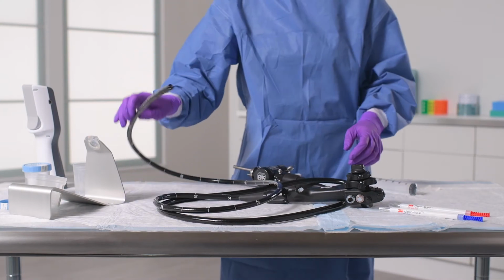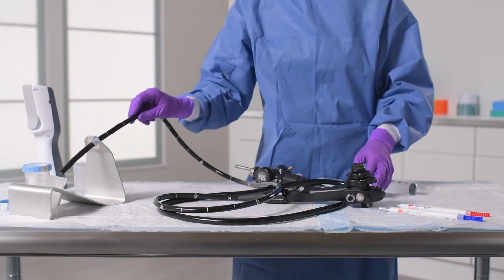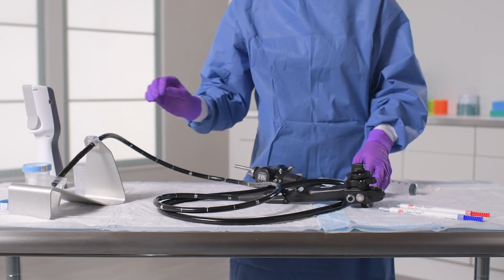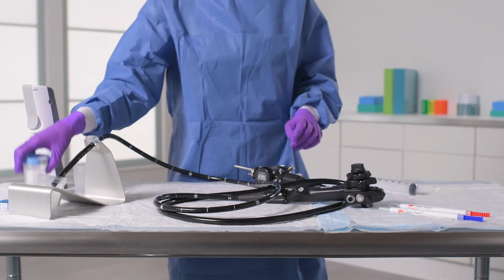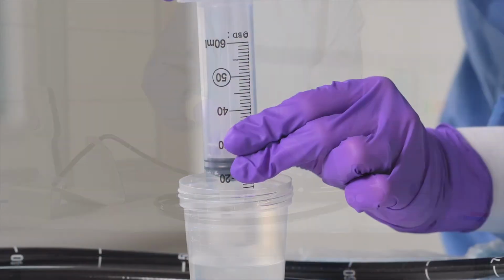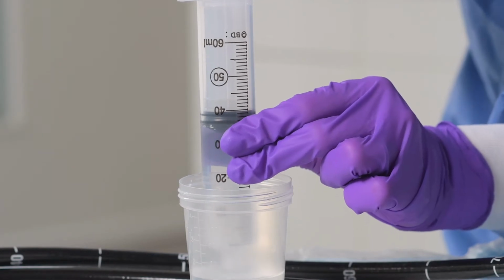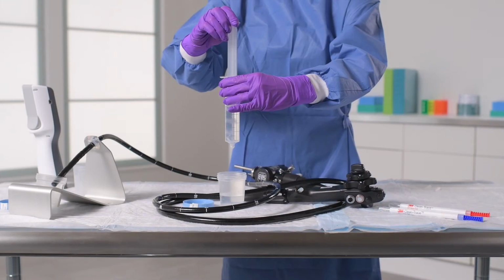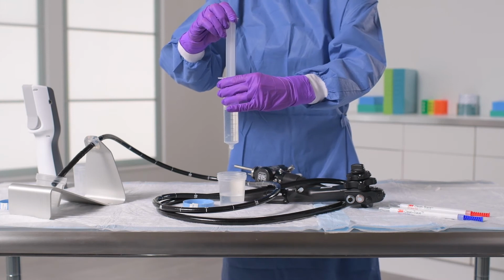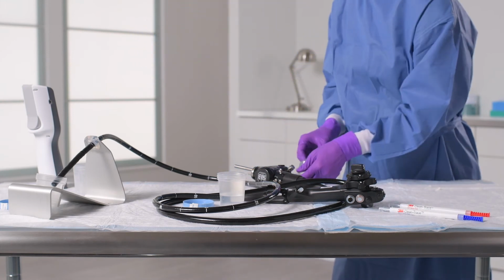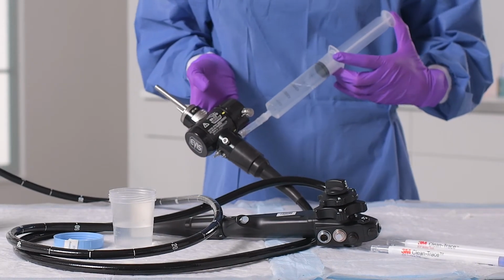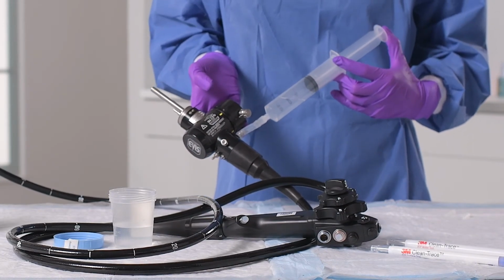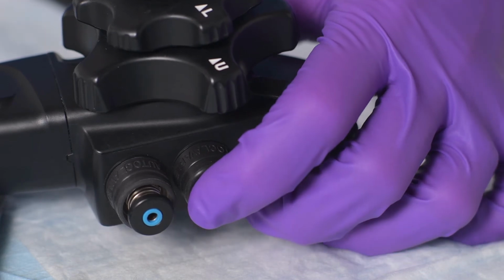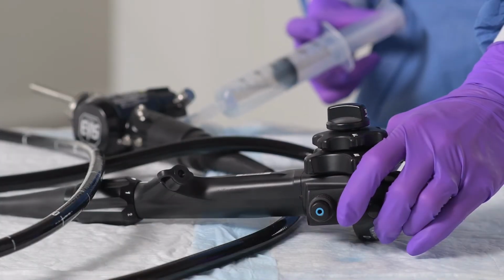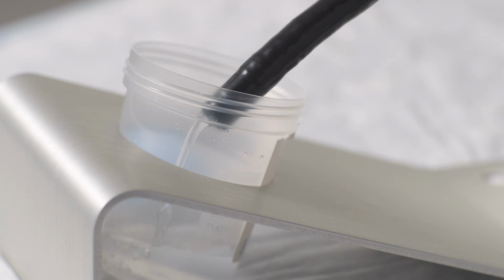First, secure the distal end into the empty sterile sample collection container. To avoid contamination, make sure that it doesn't go below the 40 milliliter mark. Next, fill your syringe with 40 cc's of sterile water and an additional 20 cc's of air. Then reattach the syringe to the connector. If using the plug, slowly press down on the syringe. Otherwise, press down on the suction valve while slowly pressing down on the syringe. The rinsate will flow through the channel and into the collection container.